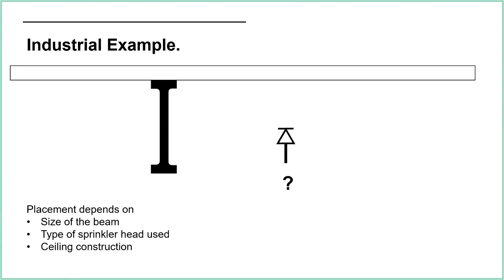What about a more industrial example? A common obstruction we come across is beams — where we don't have a flat ceiling. Sloped ceilings don't tend to cause too many issues because you design it as if it were flat and adjust the pipe length to compensate for the slope. But beams and supports — whether exposed structural beams, plasterboard-enclosed, or concrete — where the ceiling isn't flat, can cause an obstruction.